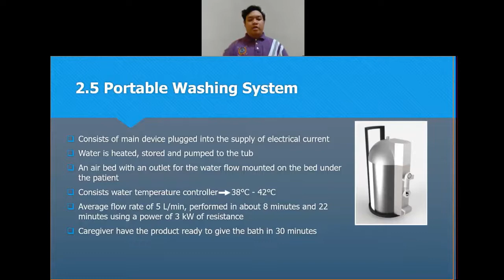Portable washing system consists of main device plugged into the supply of electrical current. Water is heated, stored, and pumped to the tub. An air bed with an outlet for the water flow mounted on the bed under the patient. Consists of water temperature controller, which is 38 degrees Celsius to 42 degrees Celsius. Average flow rate of 5 liters per minute. Performed in about 8 minutes and 22 minutes using a power of 3 kilowatts of resistance. Caregiver have the product ready to give the bath in 30 minutes.